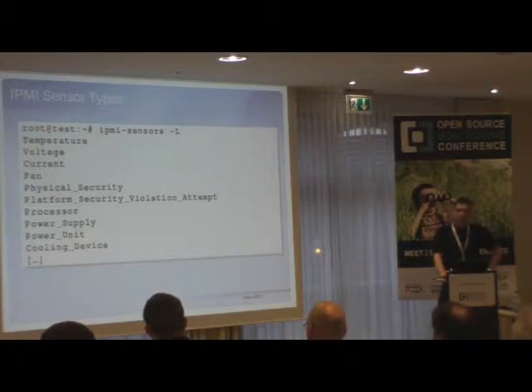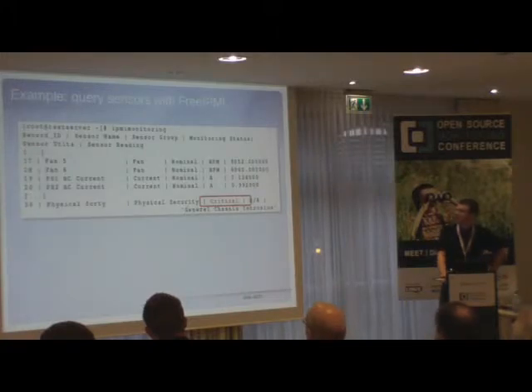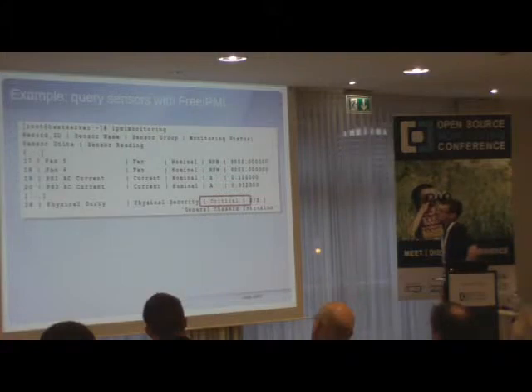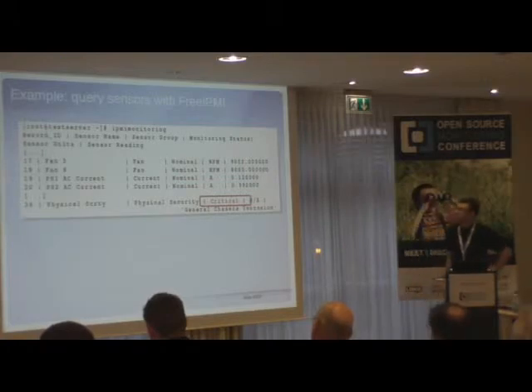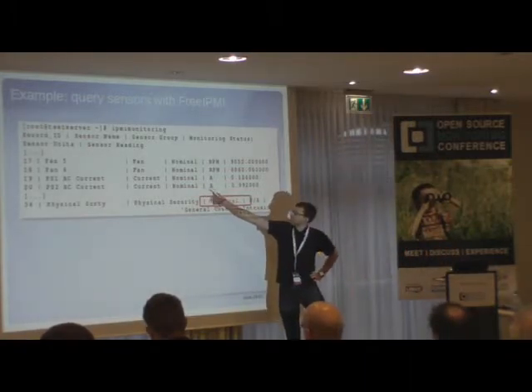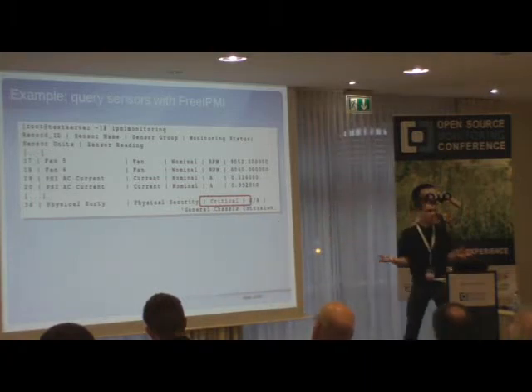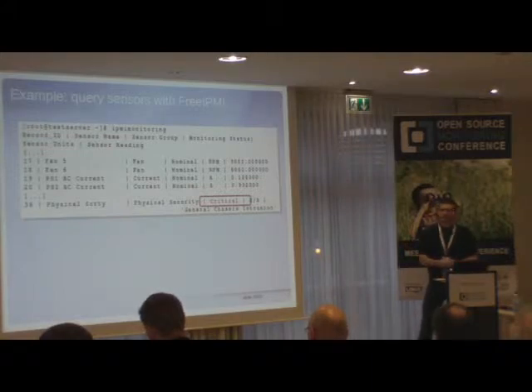We are using free IPMI — specifically the free IPMI suite, which has different kinds of tools. One of them is ipmi-sensors. You can use a command called ipmi-monitoring, which gives a list of all the sensors. The nice thing is that the fourth column tells you whether the sensor is fine or not — when it says 'nominal', everything is fine. And that was the starting point of the plugin, because this is really a good output for parsing and feeding information into Icinga or Nagios.